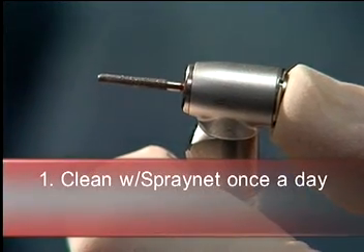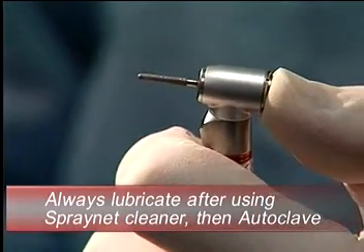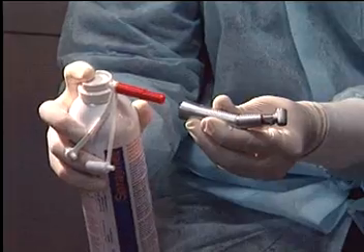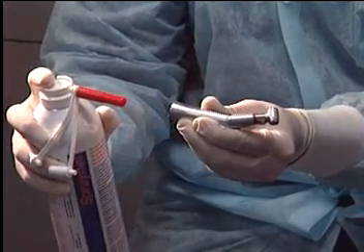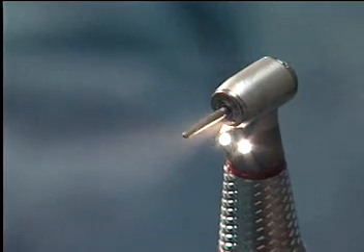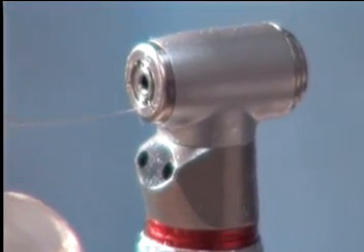Once a day, clean each handpiece with the SprayNet 500. You must always lubricate after using SprayNet cleaner, before autoclaving. Remove the burr from the handpiece, hold the can upright, and spray only once into the end of the handpiece. Reattach the motor. Replace the burr and run the Bien-Air for 20 to 30 seconds to purge. Clean the spray vents in the contra angles with the wire cleaner.